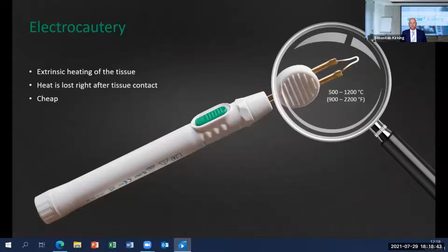Here you see an electrosurgical electrode in an infrared animation. The dark blue of the background is a tissue sample that for this experiment replaces the patient body. Both the electrode in the front and the tissue sample are blue. That means they have almost the same temperature. The electrode is now already activated. You see that in contrast to a cauter, it does not become hot. Now I closed the electric circuit by touching the tissue, and now the tissue at the point of contact becomes hot. Note that the electrode itself only indirectly became hot. The rear part of the spatula is obviously still cool.